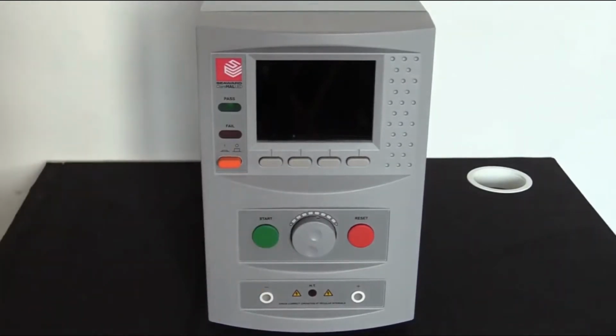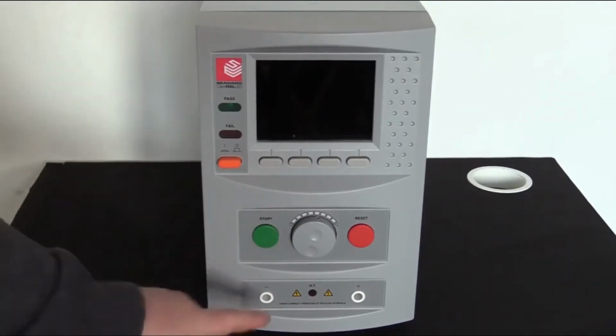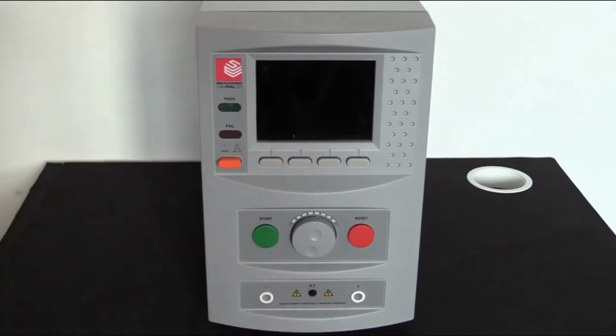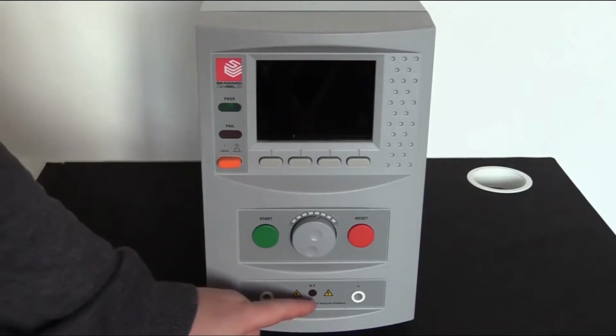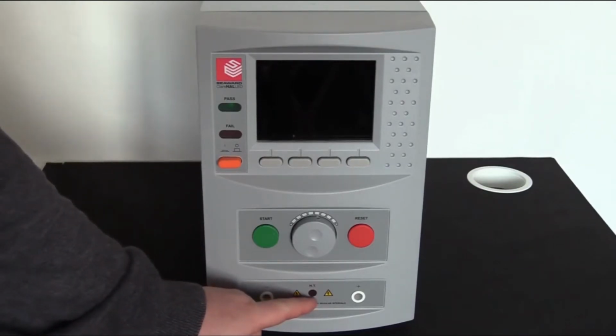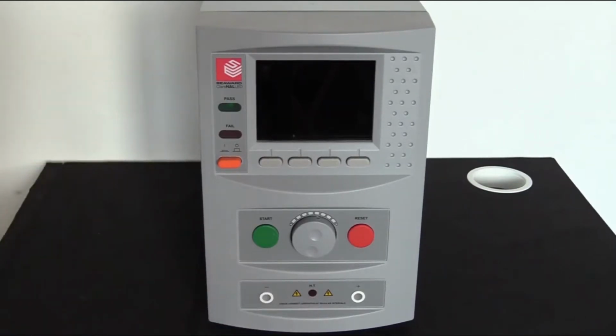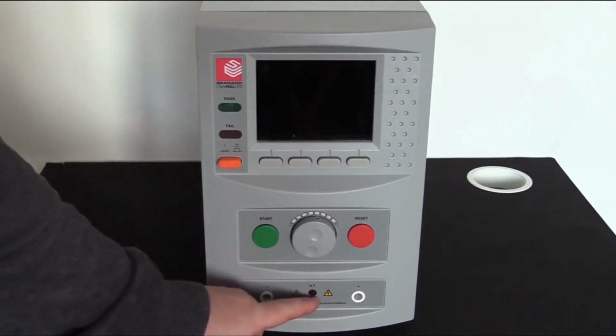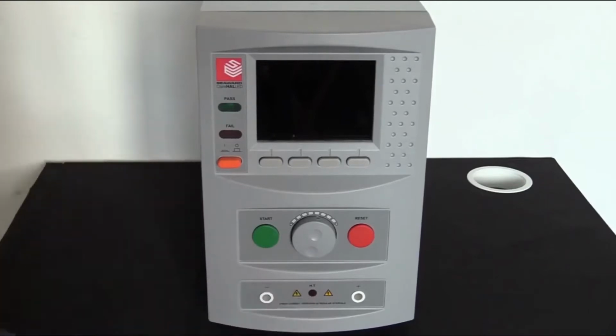And then beneath that we have some test outputs. So you'll see the 2 white ports, 1 negative, 1 positive. That's where we can make our test connections for tests such as the Hipot test or the insulation resistance test. In the middle we also have our high voltage illuminator. So at any point where the voltage is deemed hazardous, the LED will glow bright red, alerting the operators that there's potential hazards on the output test leads.